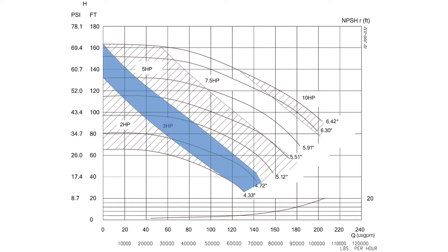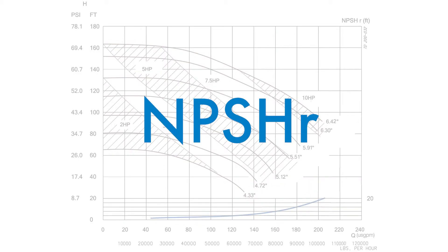This curve features a pump that can operate from 2 to 10 horsepower depending on the desired performance. On this graph, each curve represents a typical impeller size for this pump, ranging from 4.33 inches to a full-size 6.42 inch impeller.